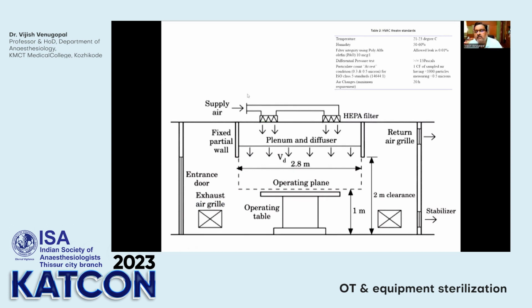Now, it is very important that we have a minimum of 20 to 24 air changes in the theater. The temperature and humidity should be maintained, and the leak test and the air velocity test should be done to test the integrity of the HEPA filter. You should do it at least once in 2 to 3 years, depending on the usage of the theater. And the leak allowed is 0.01%. It is done using the polyalpha olefin test.